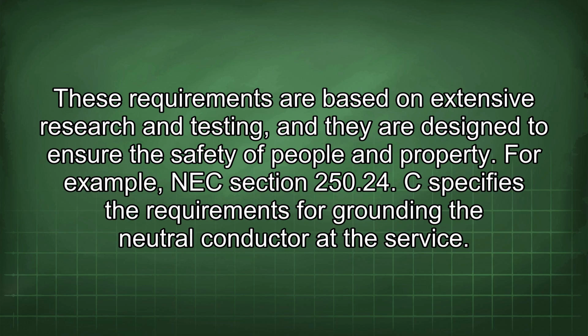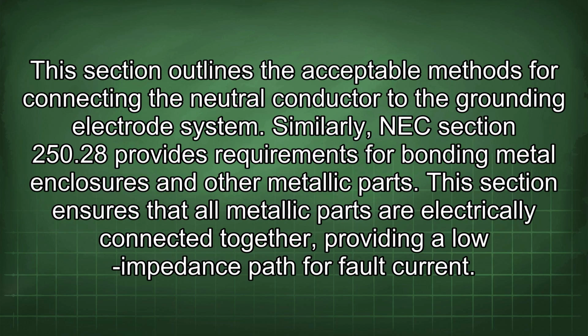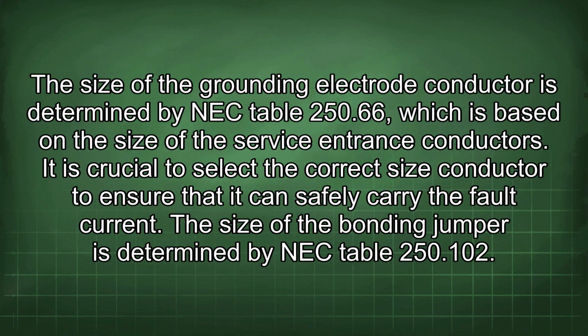250.24(C) specifies the requirements for grounding the neutral conductor at the service. This section outlines the acceptable methods for connecting the neutral conductor to the grounding electrode system. Similarly, NEC Section 250.28 provides requirements for bonding metal enclosures and other metallic parts. This section ensures that all metallic parts are electrically connected together, providing a low impedance path for fault current. The size of the grounding electrode conductor is determined by NEC Table 250.66, which is based on the size of the service entrance conductors.